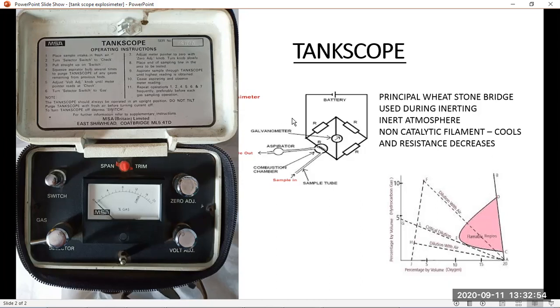Then the main principle of the Tankscope is the Wheatstone bridge, where when all the resistances are balanced, there is no current flowing. Now in the Tankscope, we use a non-catalytic filament or metal coil coating. What happens is this element cools down in the presence of hydrocarbon gas.